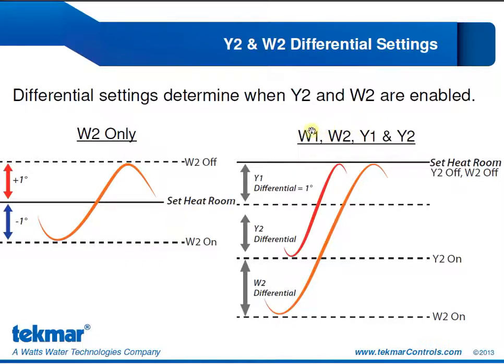If we are using W1, W2, Y1, and Y2, so an example of this would be radiant floor as first stage, heat pump as second and third stage, electric strip backup as fourth stage. Our W1 will be operating with PWM, pulse width modulation. Our second stage of heat, our Y1, has a fixed differential of 1 degree. So when we are 1 degree below that set heat room, our Y1 will be enabled.